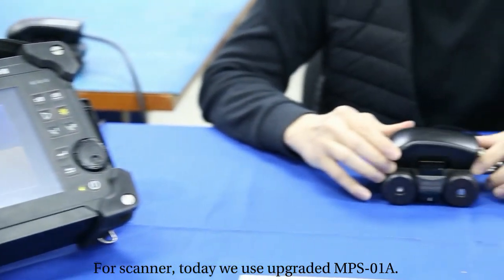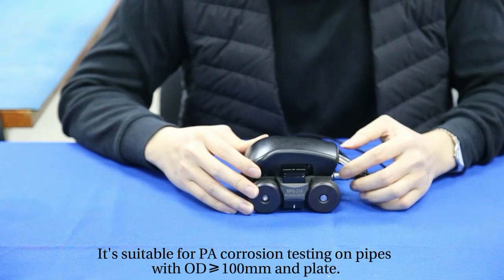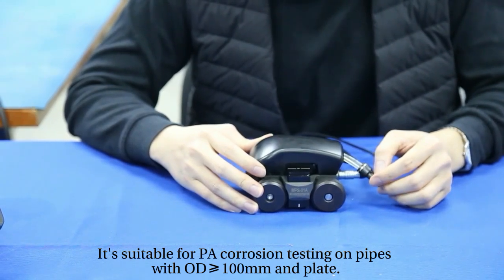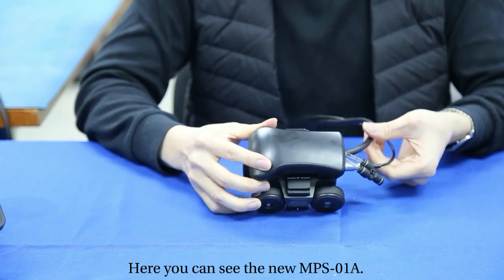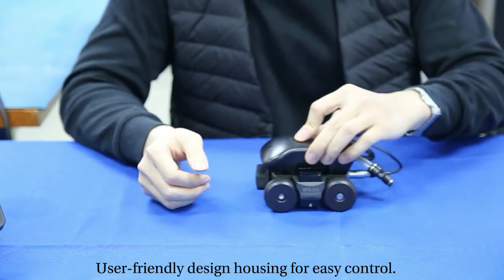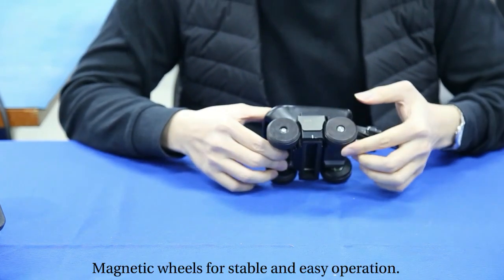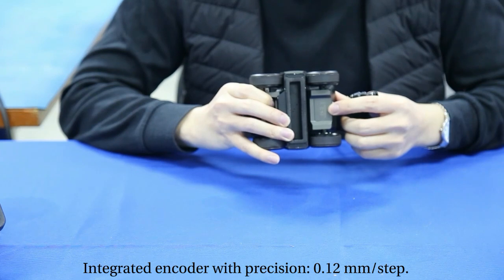For the scanner, today we use the upgraded MPS01A. It's suitable for PA corrosion testing on pipes with outside diameter larger than 100 millimeter and plate. Here you can see the new MPS01A — user-friendly design housing for easy control, magnetic wheel for stable and easy operation, and integrated encoder with precision 0.12 millimeter per step.